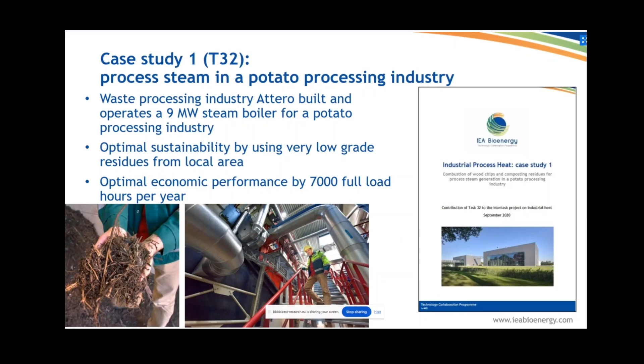The first case is where natural gas-based process steam generation was replaced by process steam generated from locally available residues. You can see on the bottom left a picture of the fuel used here—a very low-grade type of wood residue from a composting process, the sieve overflow, available for free. It's used in a dedicated boiler for at least 7,000 full load hours per year, so you have a relatively expensive installation but with a very cheap fuel, used for continuous steam generation—very reliable and ideal for 24/7 operation.